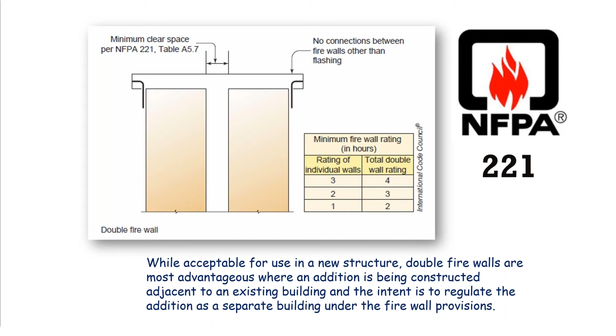We've had designs come in where they say, oh, I can use NFPA 221, I've got a 3-hour, here's a 3-hour fire barrier. A 3-hour fire barrier is not equivalent to a 3-hour firewall. Remember, this is double, so you're doubling that wall when you're using NFPA 221. And again, it helps out with existing because it's just easier to construct.